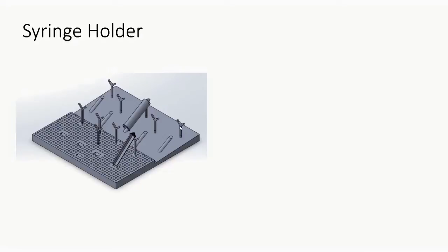Now, for the syringe holder, two different holders are shown, one for the plunger and one for the syringe. It is held at an angle so that the camera can pick up the whole parts of it. However, if you notice, the holder where it holds the syringe area does not have any hole for drainage. This is mainly because it may cause an error for the camera as it may pick up as a dirty spot.